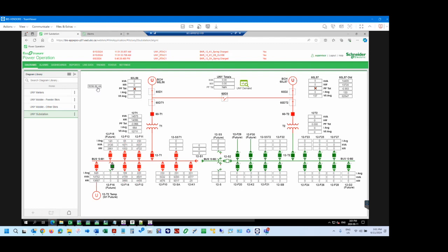Those parameters, the registers, were given to me by the PLC guy as read-writable Modbus registers or addresses. So I could make a read-writable register in my map, and then in the diagram I linked a pop-up that allows you to control a value. Basically you click on this, for example, and it gives you a small pop-up that says, okay, enter your value. You write the value, kind of like the button, but instead of operating a breaker, you're entering a value.